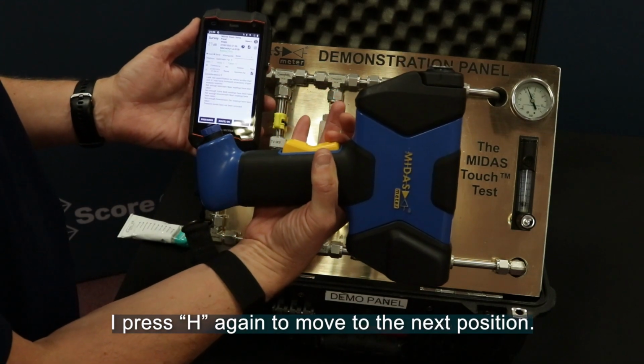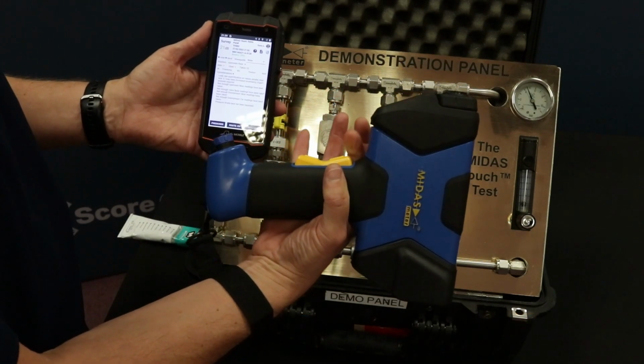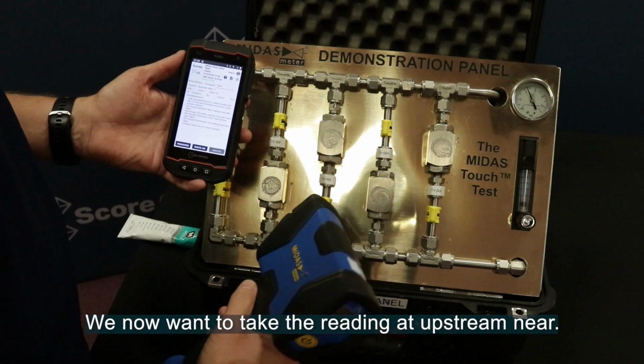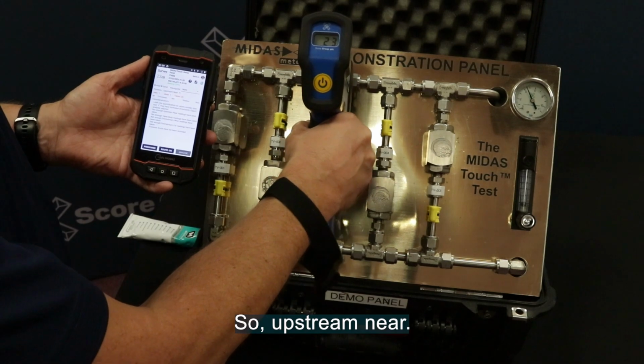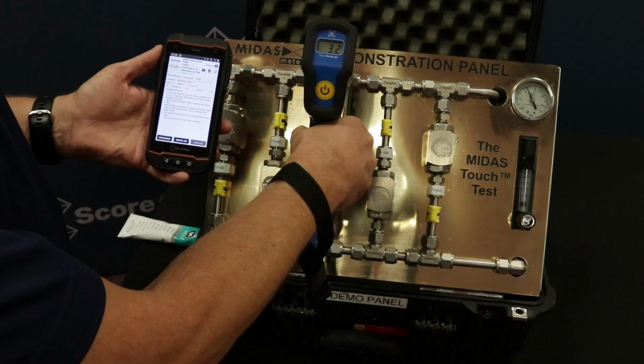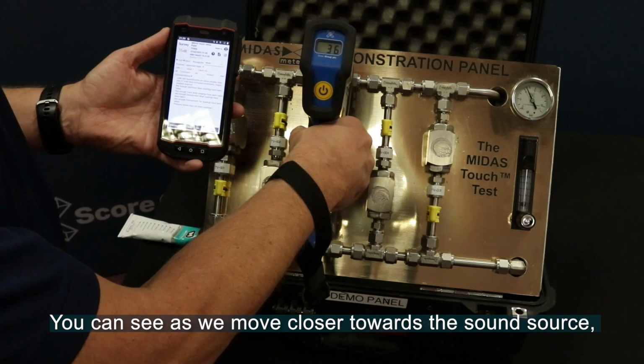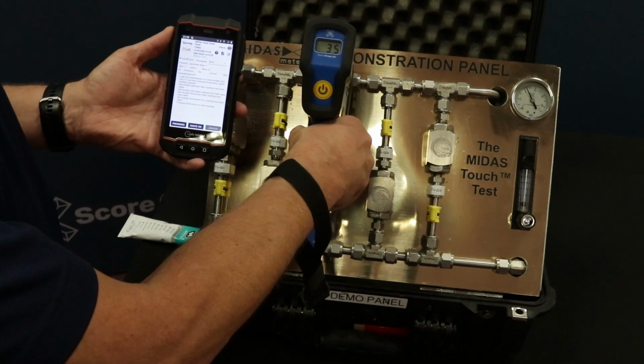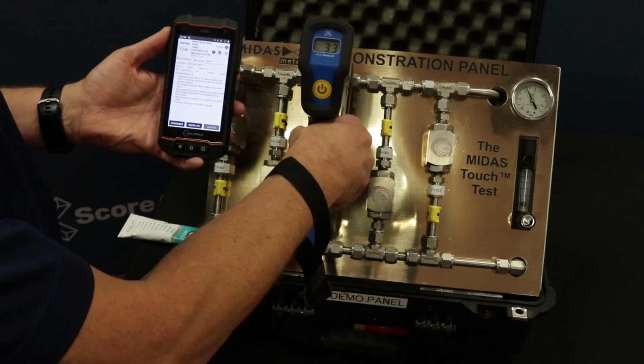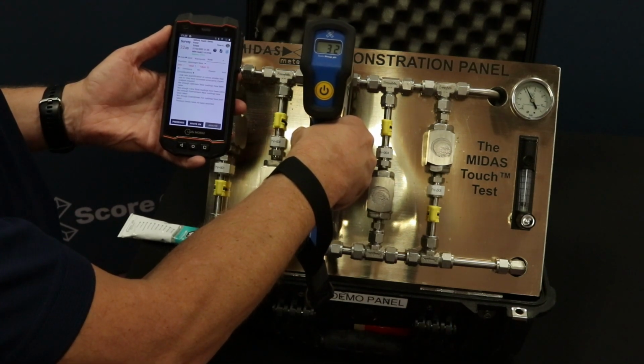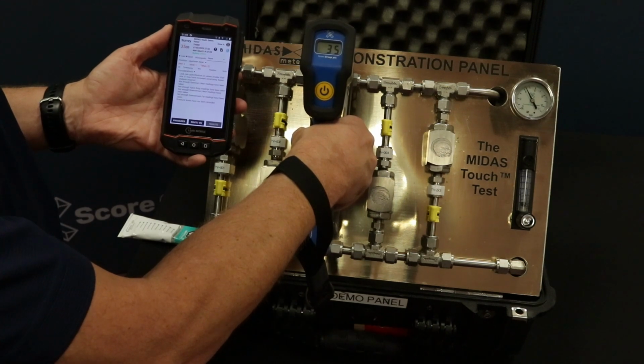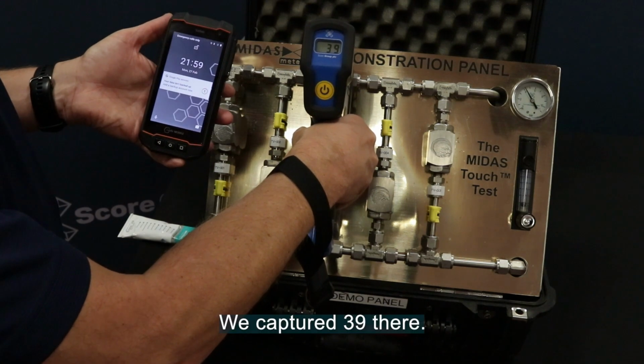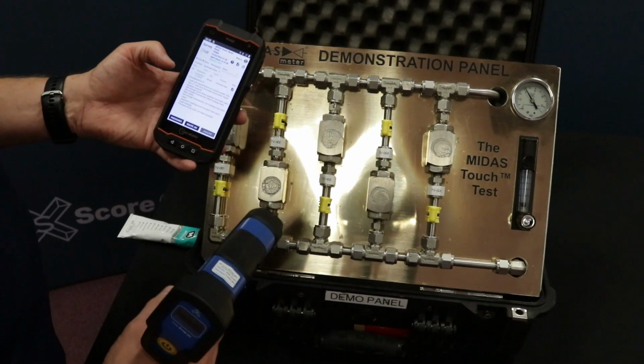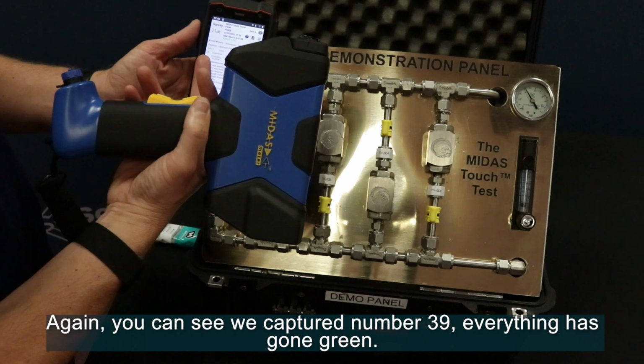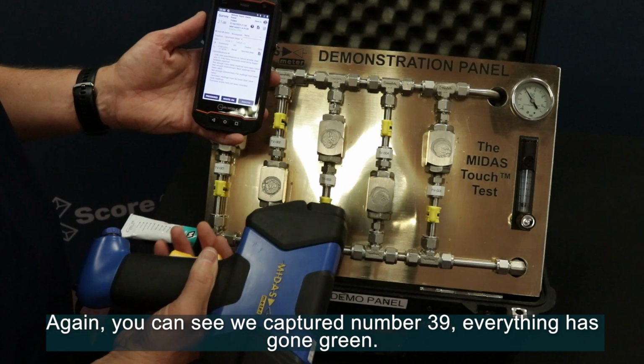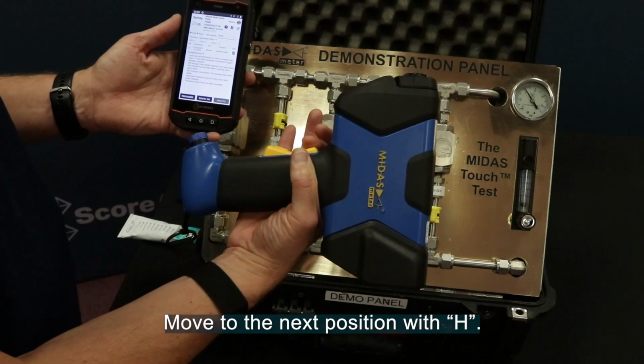I press H again to move to the next position. We now want to take the reading at upstream near. So upstream near. You can see as we move closer towards the sound source, the decibels are increasing. Just let it stabilize there. We capture 39 there. Again, you can see the captured number 39, everything's gone green. Move to the next position with H.